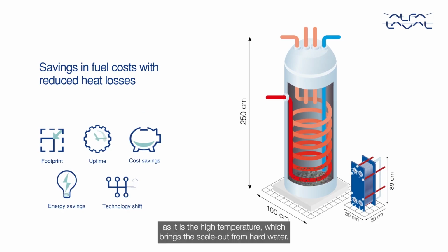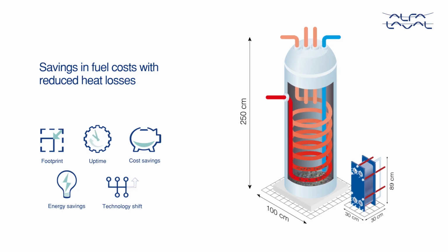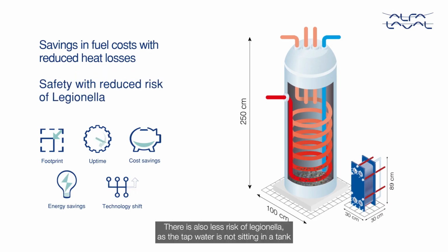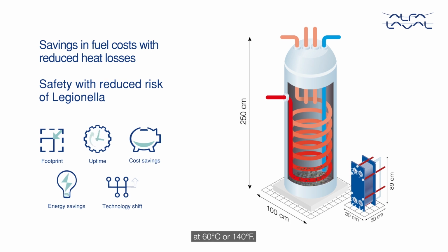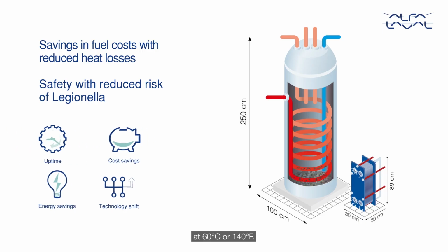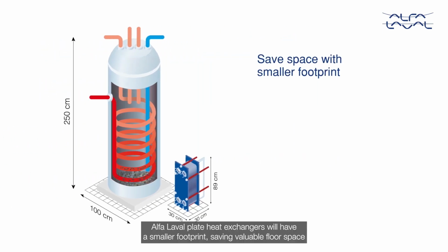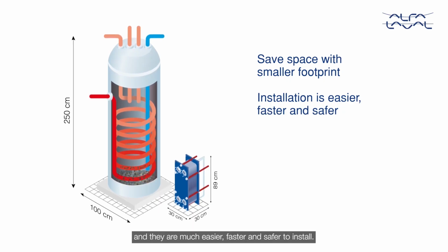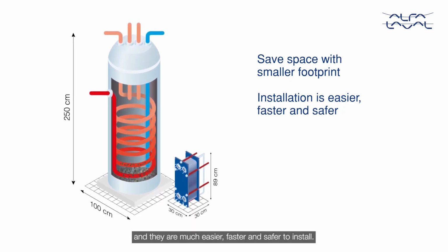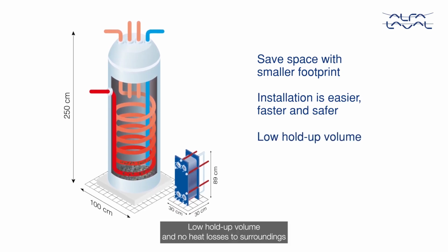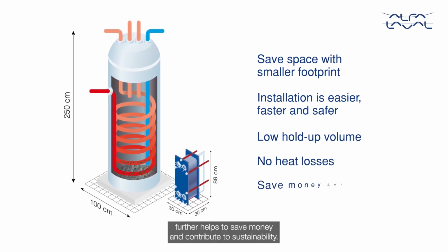This is especially important with steam heating tap water, as it is the high temperature which brings the scale out from hard water. There is also less risk of Legionella, as the tap water is not sitting in a tank at 60 degrees Celsius or 140 degrees Fahrenheit. Alfa Laval plate heat exchangers will have a smaller footprint, saving valuable floor space, and they are much easier, faster and safer to install. Low hold-up volume and no heat losses to surroundings further helps to save money and contribute to sustainability.